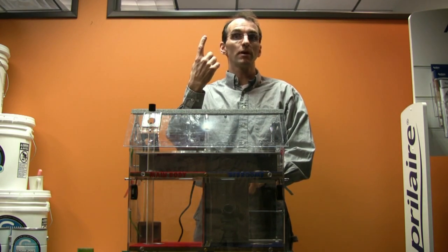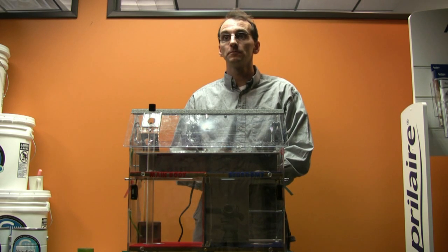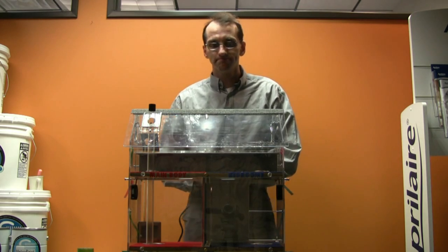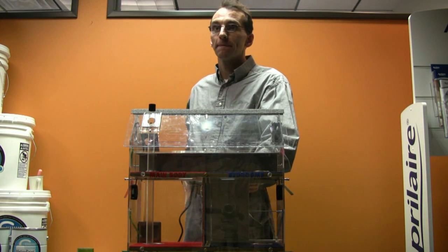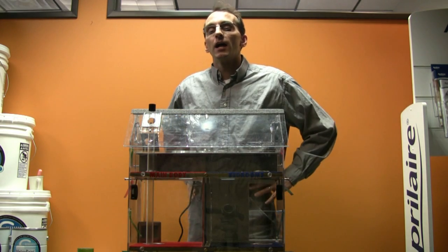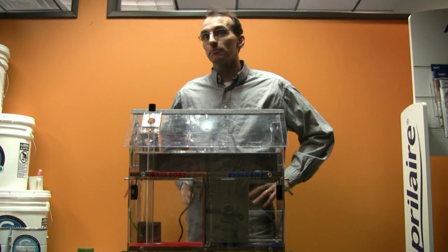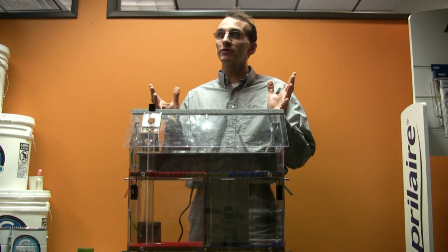Okay. That's your problem. So the only way to seal that would be similar to sealing your heat supply. You'd have to tape off, because typically the framers will enclose the bay of a joist system or your stud cavities as your cold air returns in modern construction. Is that taping off? Taping actually is not the preferred method. The preferred method is to use mastic on all your ductwork.